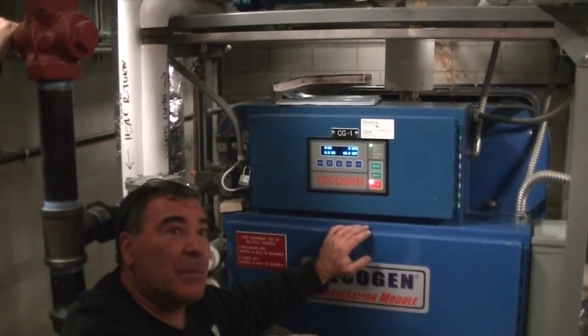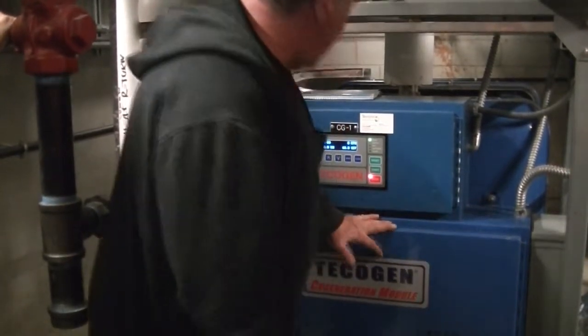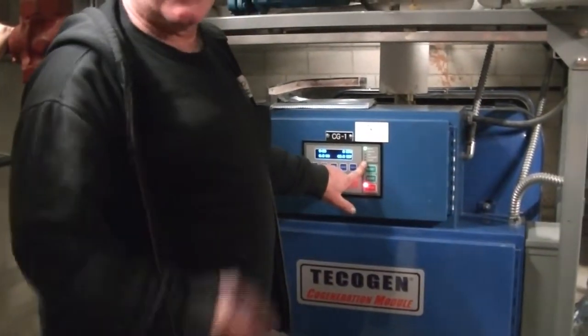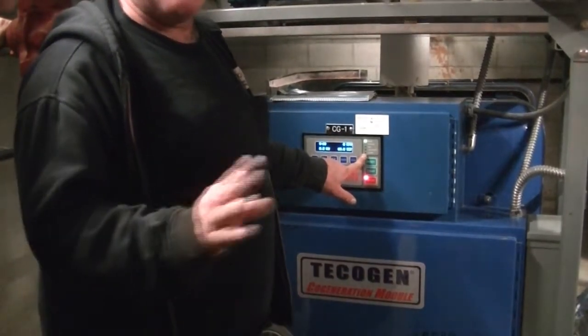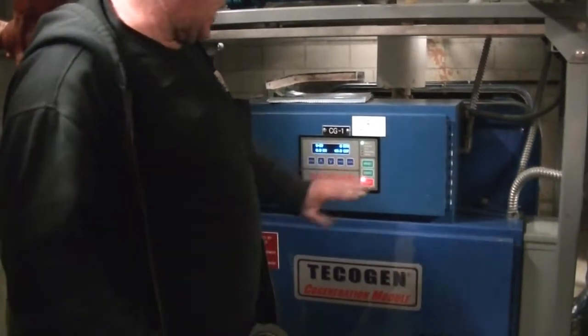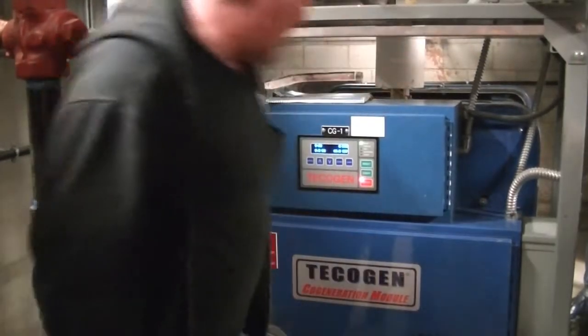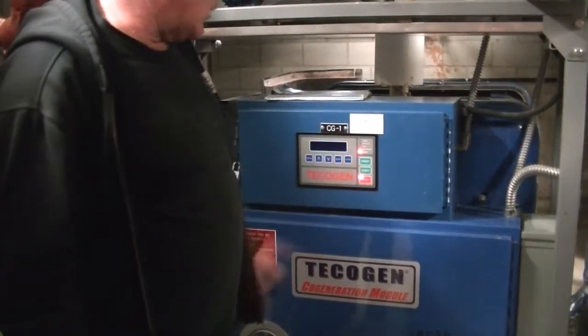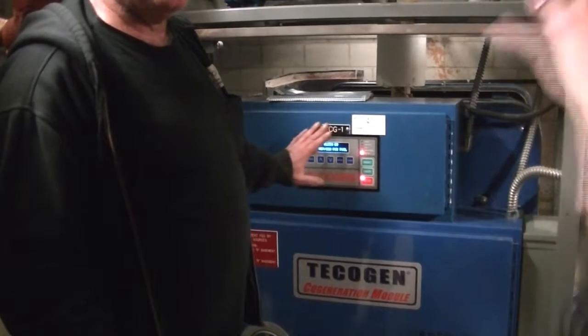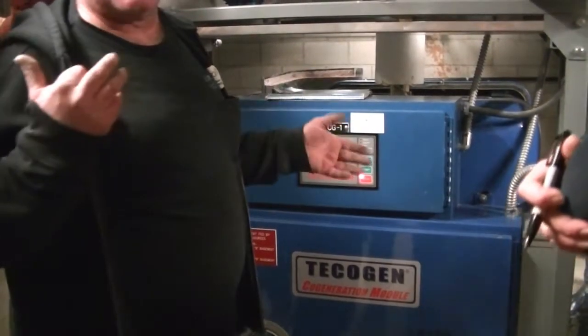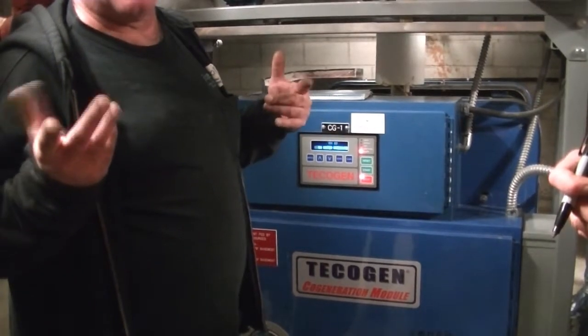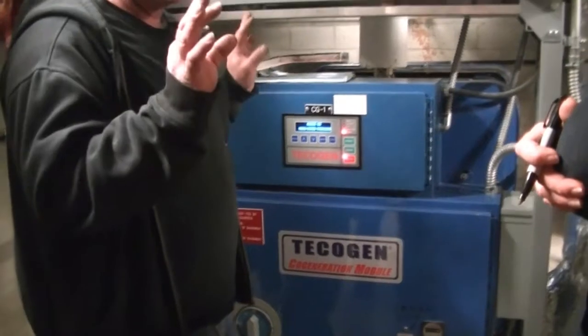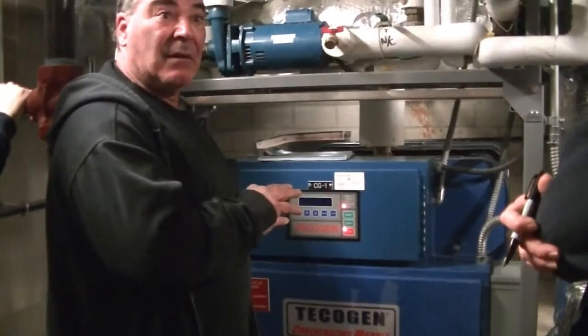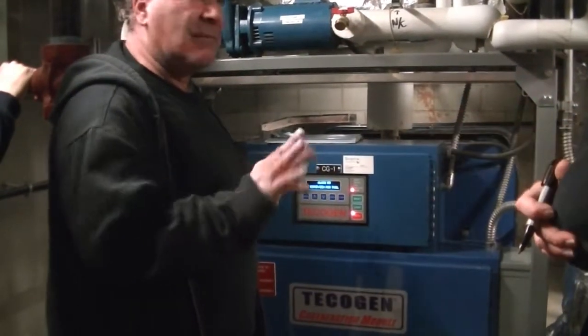When are we calling you? When that light turns red and it stays on, it doesn't blink or flash, nothing. Like that. And you'll see the alarm. So low thermal load, it's blinking? Yes. Also an emissions fault alarm will blink. Pre-alarm, they call it. It'll flash like that. It'll say emissions alarm, but it'll still be running. So a solid red light, we're calling the cogen company.